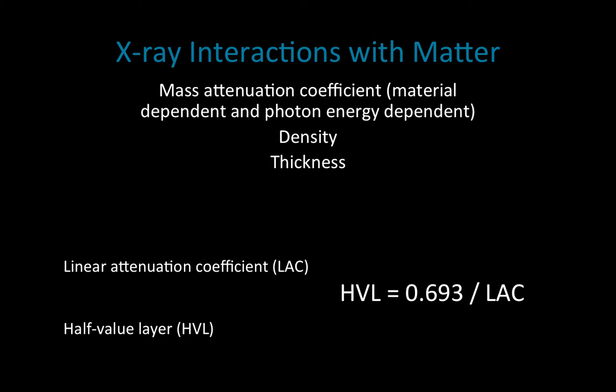That's why our lead aprons used in interventional radiology are relatively thin. If you wanted to achieve the same amount of shielding with a different material, the thickness required would be too much and we wouldn't be able to achieve that. The linear attenuation coefficient relates to the half value layer in that sense, but the LAC is a little more complicated to calculate, so the half value layer comes in handy for a lot of calculations.